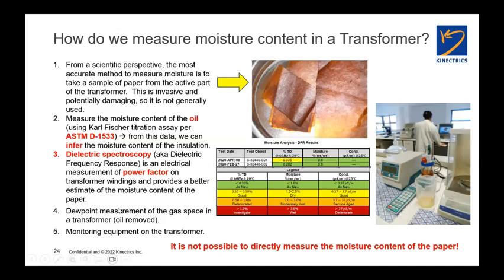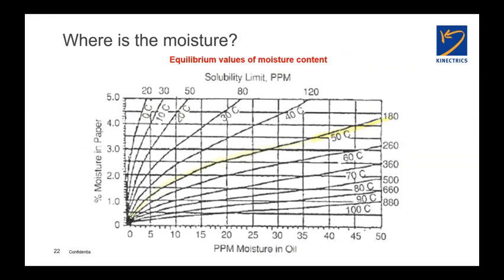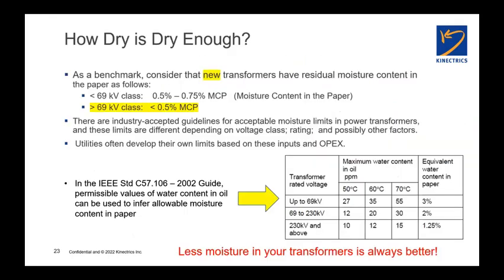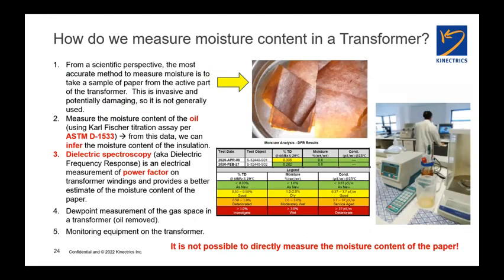So what do we do instead? Well, the industry standard: we take an oil sample and we do what's called a Karl Fischer titration test, which goes by the ASTM test procedure D1533. That gives us the parts per million of water in the oil. And if I've been smart and taken the temperature of the oil sample, I can go to my Oommen curve and get my moisture content in the paper.